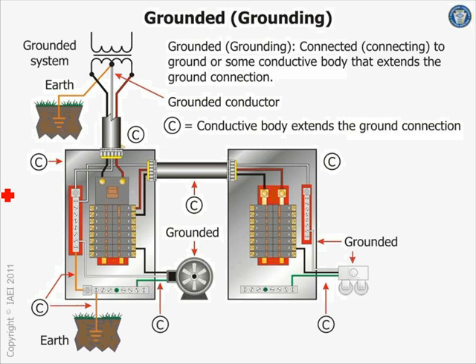You're running a grounded system and grounded equipment, and the two of them are referenced together to Mother Earth. And the two are also tied together through the neutral. Can you see that? The neutral takes this ground, that's the highway, like the interstate, let's say Interstate 494, coming from here all the way to this ground, and bonds the two grounds together.